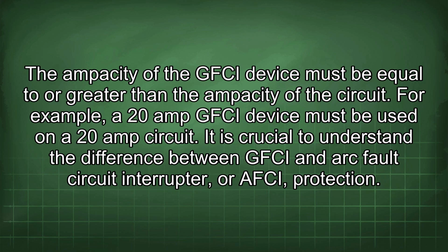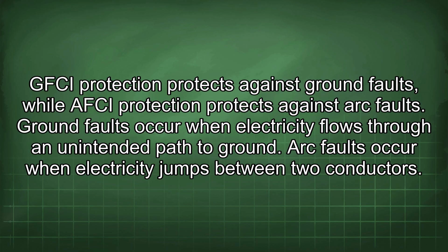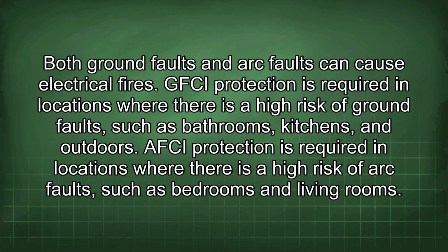It is crucial to understand the difference between GFCI and arc fault circuit interrupter, or AFCI, protection. GFCI protection protects against ground faults, while AFCI protection protects against arc faults. Ground faults occur when electricity flows through an unintended path to ground. Arc faults occur when electricity jumps between two conductors. Both ground faults and arc faults can cause electrical fires.